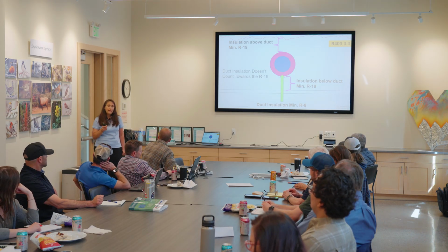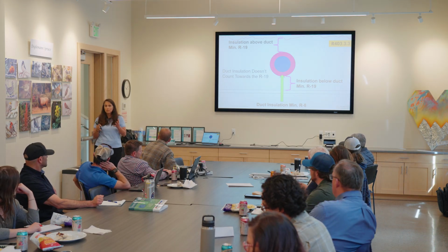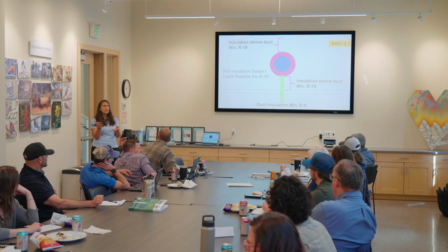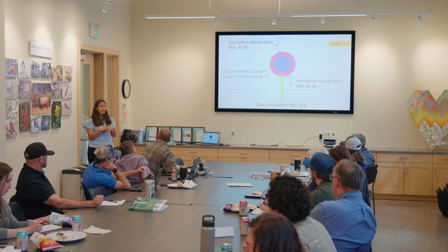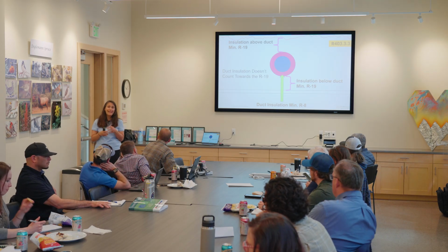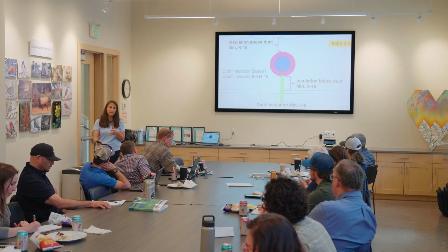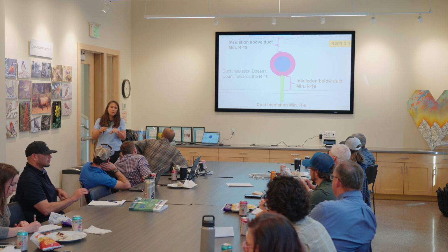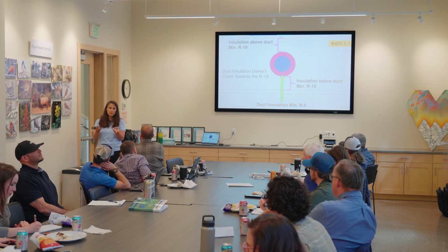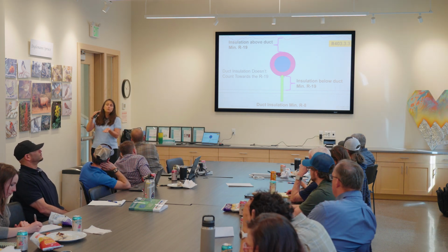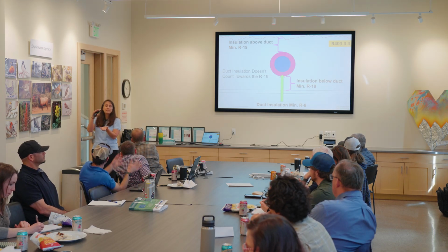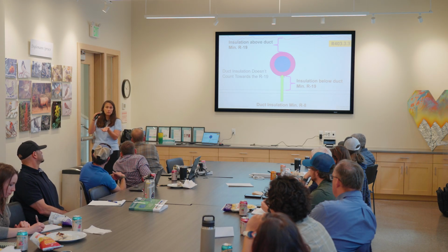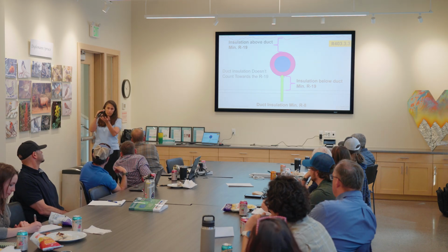That is a really good question. When this came into the code, I think it was the 2018 edition that it came in. The people who brought it forward had a lot of building science behind it. When they were doing all of their calculations to demonstrate that it basically functioned the same as if it was inside conditioned space, it was to have the R19 below it. Okay.